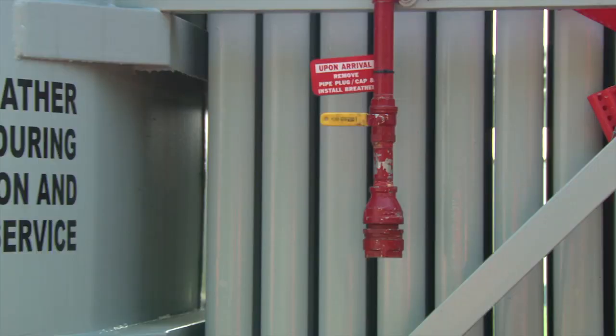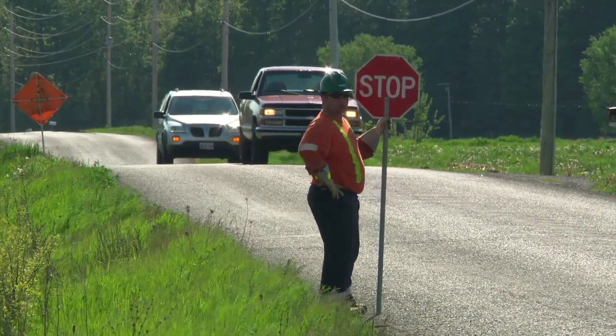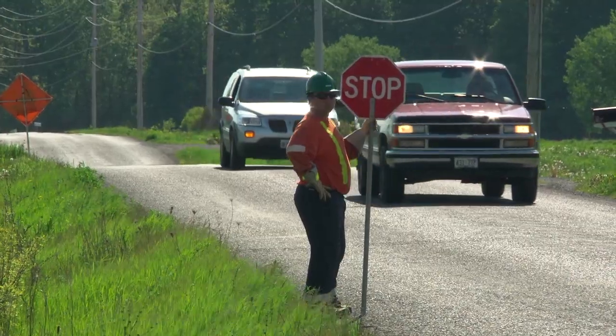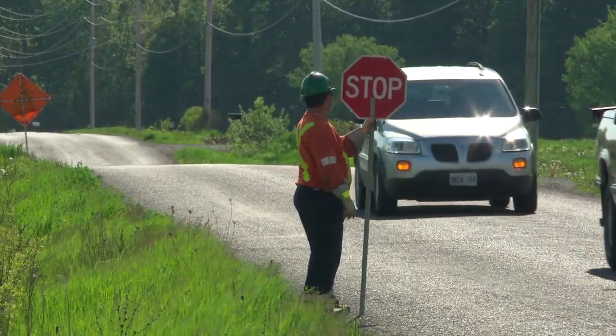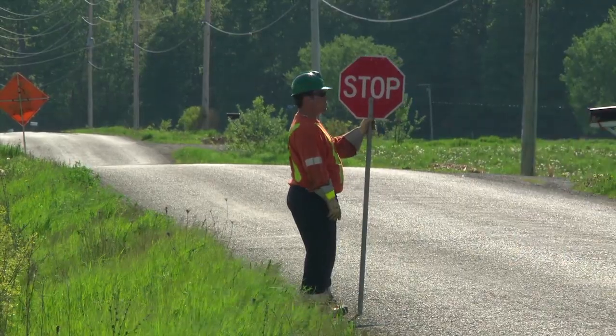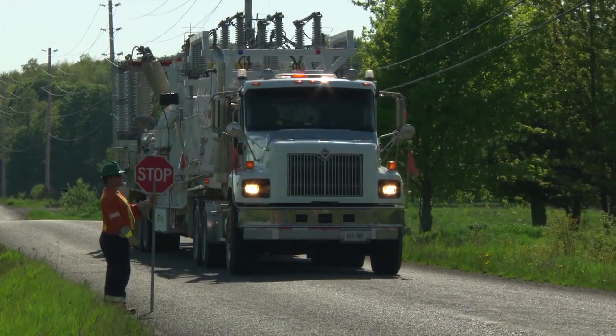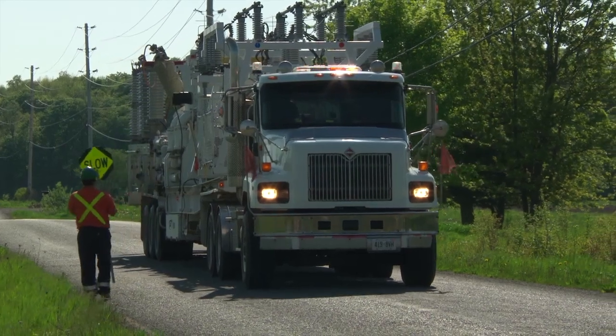The most critical step in preparing the MUS for transport is closing the breather. If the unit is going to be stored overnight during transit, arrangements must be made by the shipper to relieve any pressure buildup on the unit at its storage site. Just like receiving the MUS, when shipping it from the DS, arrangements must be coordinated with the driver, a traffic control plan prepared, and sufficient workers should be on site for traffic control.